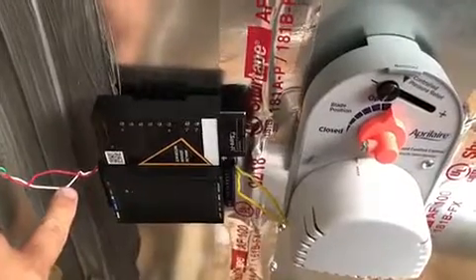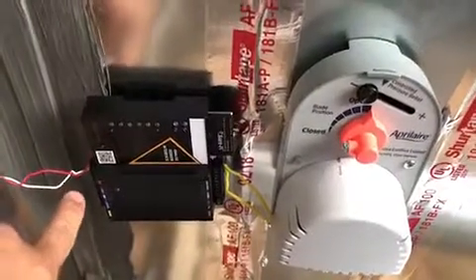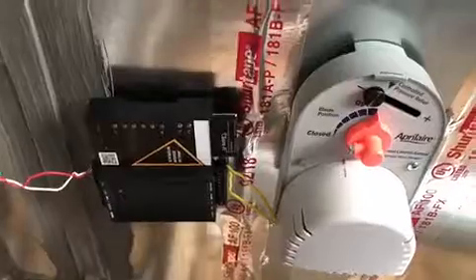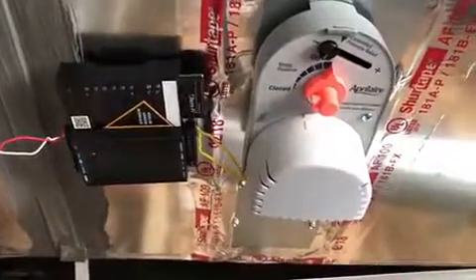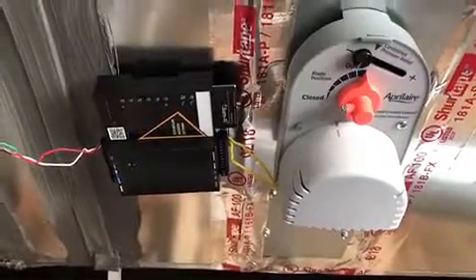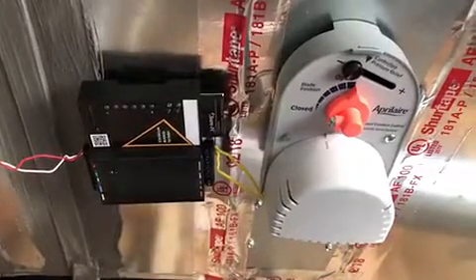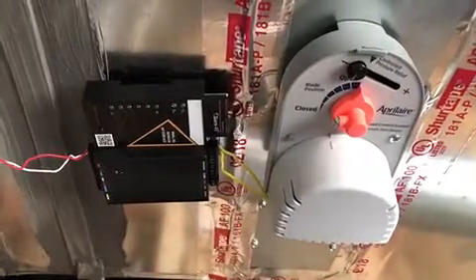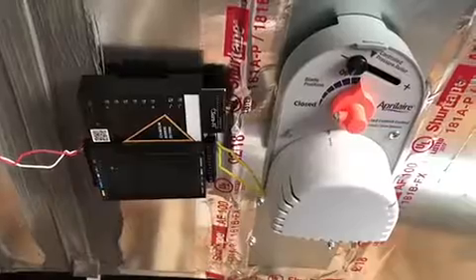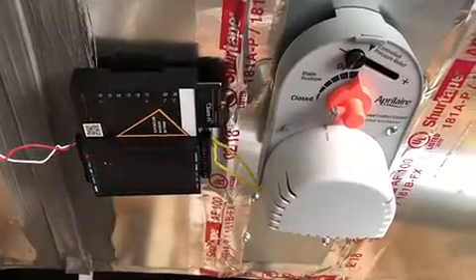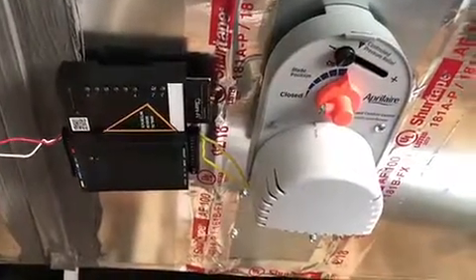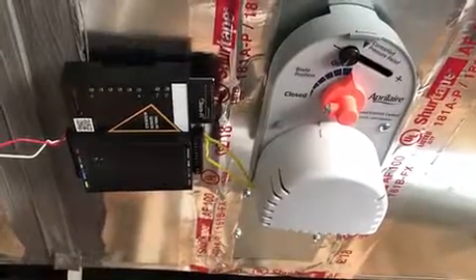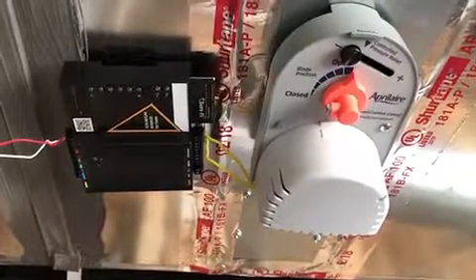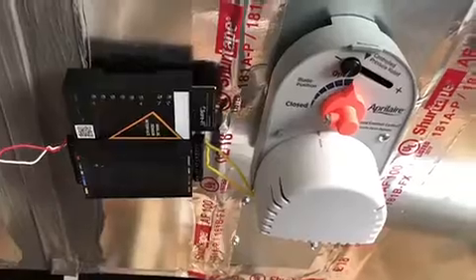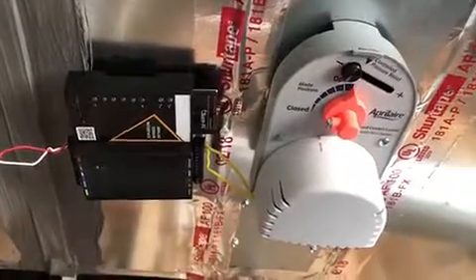This is just the other side. We've got it powered here off of another piece of HVAC equipment that's 24 volts AC, and connected into the 24 volt zoning damper here. You have this controlling the damper in this situation, but you also can use it for really any kind of sensors coming back the other direction, whether that's CO2 sensors or humidity or temperature, anything with variable voltage, variable milliamp, or a thermistor. And that's up to 6 sensors coming back depending on their type.